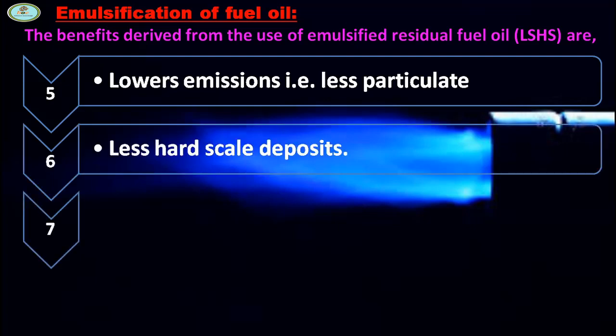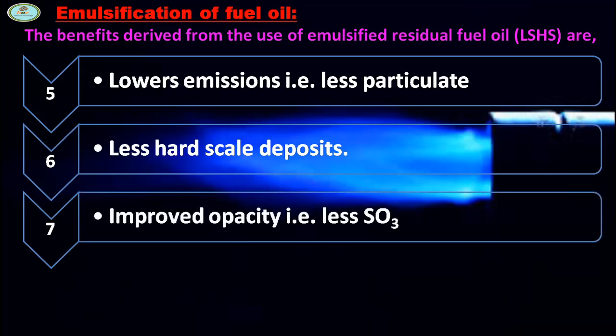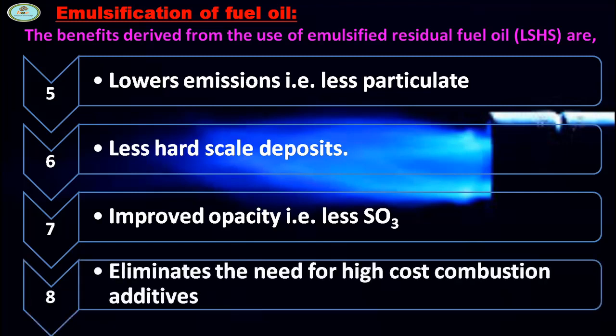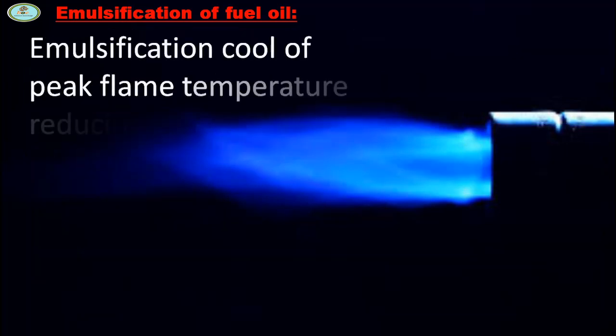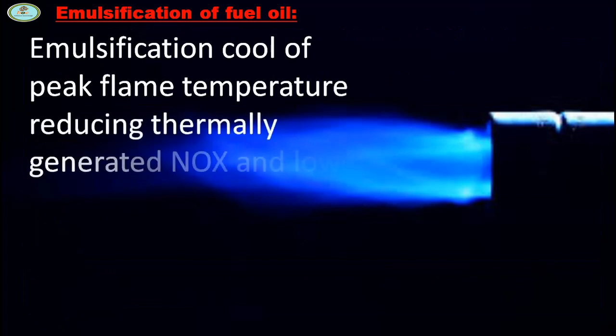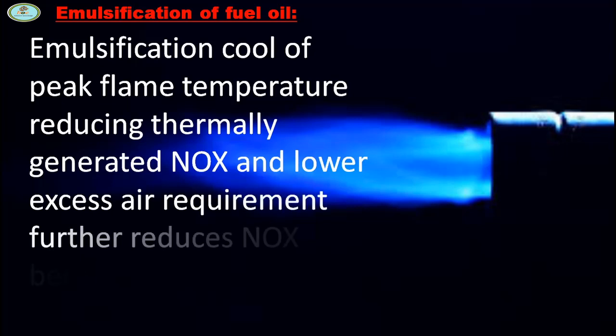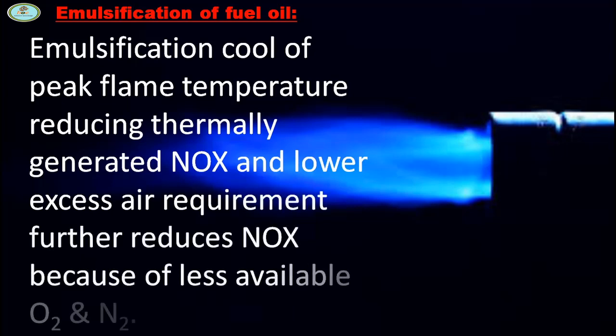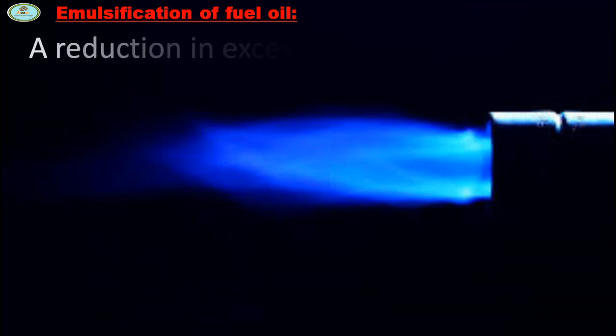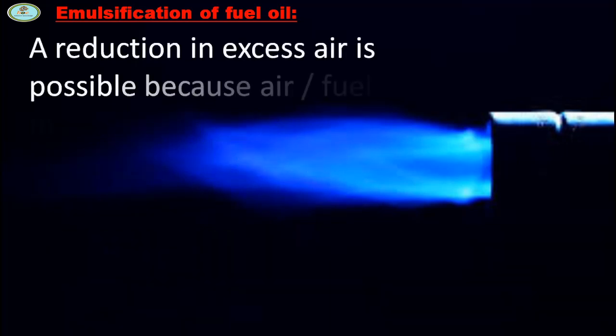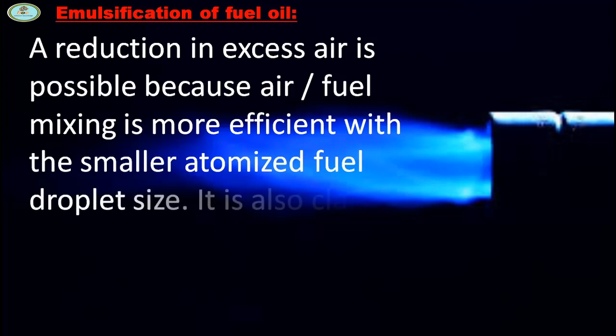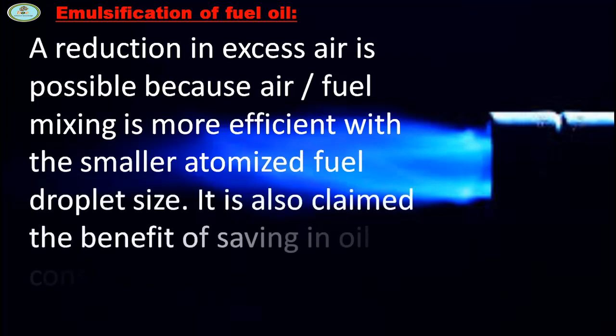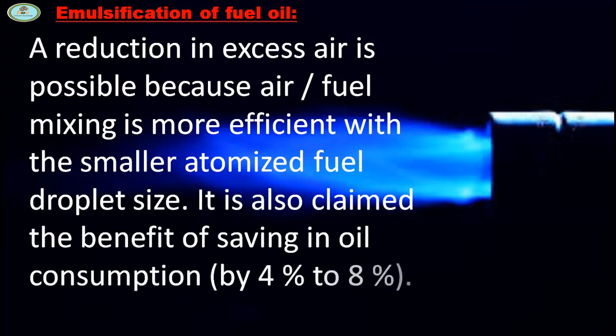Further benefits include reduced operating and maintenance costs, lower emissions, less particulate, less hard scale deposits, improved opacity, less SO3, and elimination of the need for high-cost combustion additives. Emulsification also cools peak flame temperature, reducing thermally generated NOx, and lowers excess air requirements, further reducing NOx because of less available O2 and N2. A reduction in excess air is possible because air-fuel mixing is more efficient with the smaller atomized fuel droplet size. It is also claimed that there is a saving in oil consumption of 4 to 8 percent.